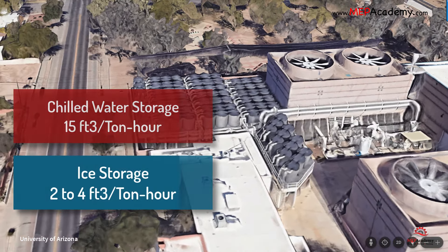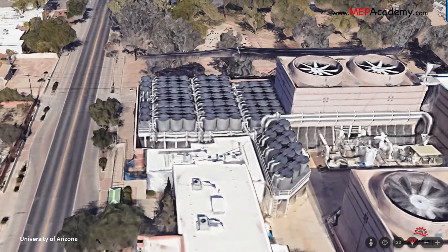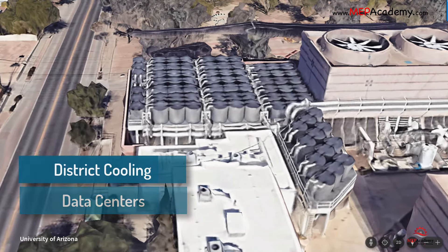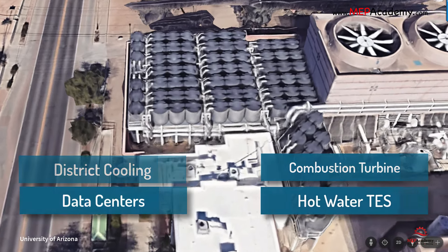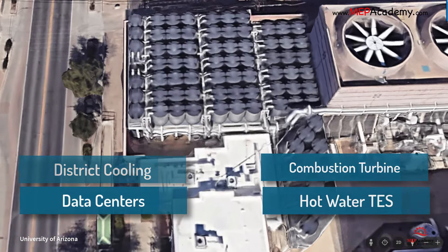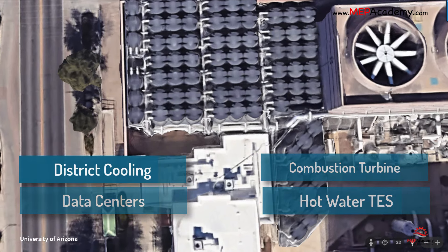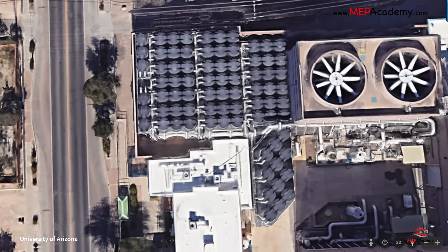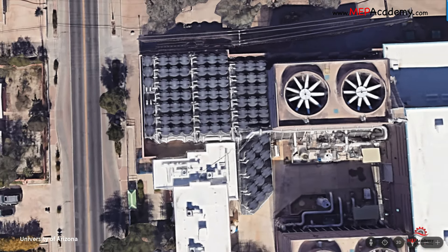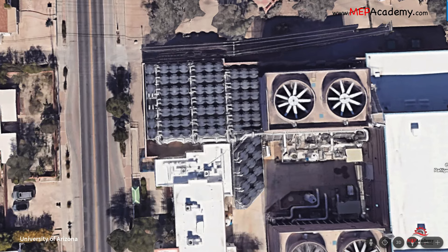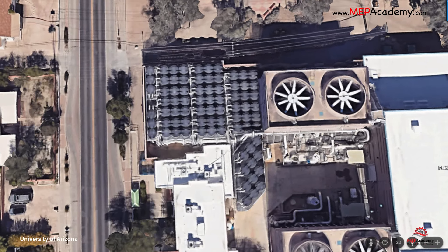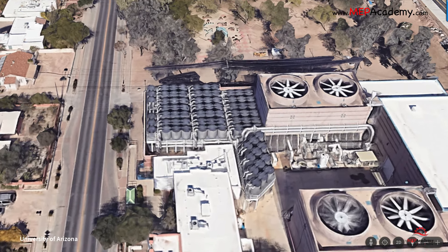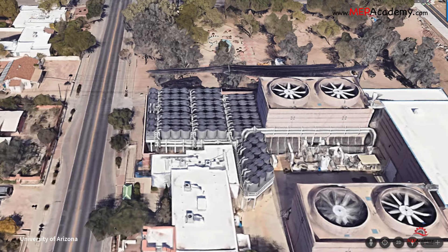The application for energy storage systems varies by industry and can include district cooling, data centers, combustion turbine plants, and the use of hot water TES systems. Utilities often structure their rates to coincide with their need to reduce loads during peak usage periods. Producing ice or chilled water at night can also increase the efficiency of the overall system, as ambient temperatures are cooler at night. This is especially true with the use of air-cooled chillers.